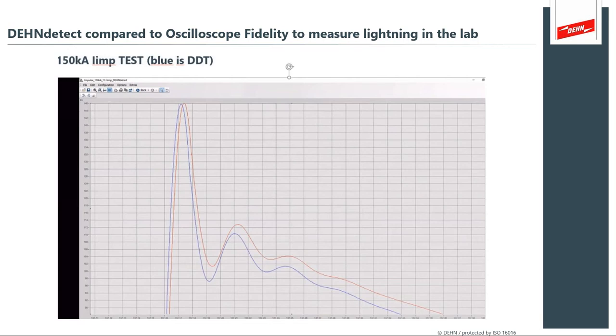There are a lot of questions about how accurate the device is. It's actually very high fidelity. The Rogowski coils measure just about as accurately as an oscilloscope in a lightning lab test. We're able to show the same peak and exactly the same trend of the actual lightning measurement. As mentioned earlier, this is a very effective and high-fidelity measurement system for capturing data.